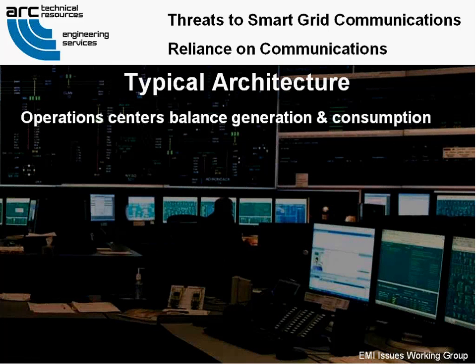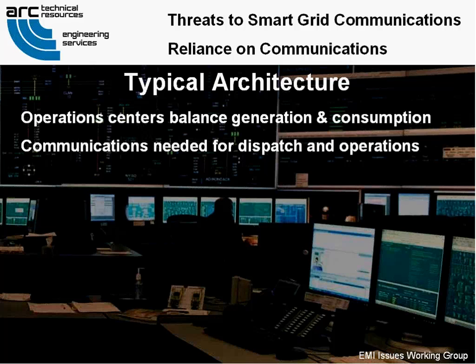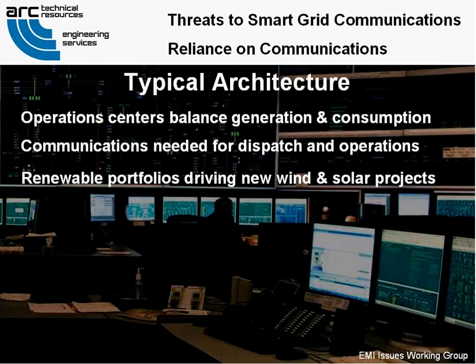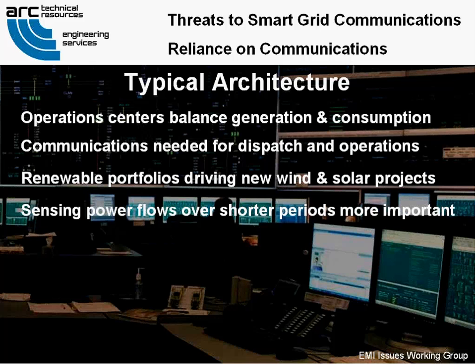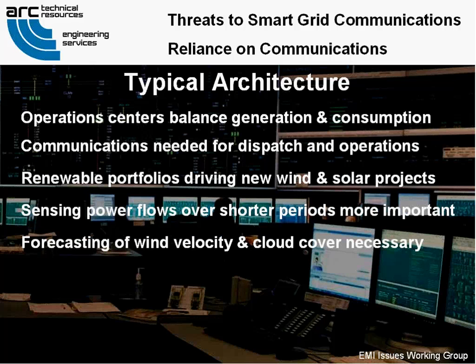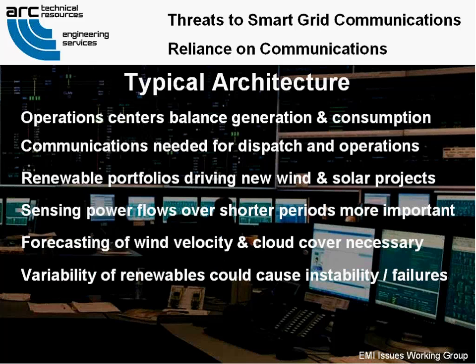Every large power company has a network operations center where people keep the generation and consumption of power in balance. They use diverse communications networks and media to dispatch resources, supervise substations, and react to faults. As more renewables come online to replace more constant forms of generation, sensors that track actual power flows over shorter periods of time will become more important. Short-term forecasting of wind velocity and cloud cover will become more necessary, as variability in renewables could cause instability if alternate power sources cannot be dispatched quickly.